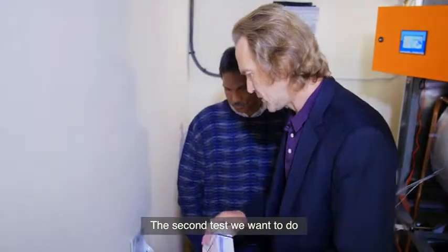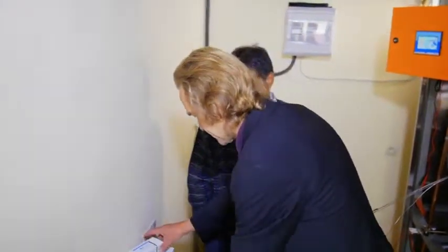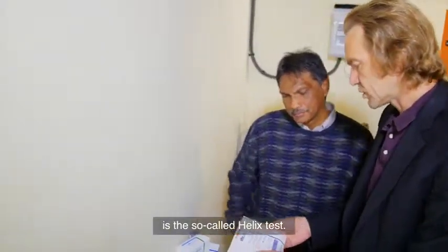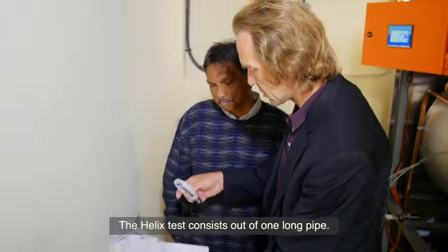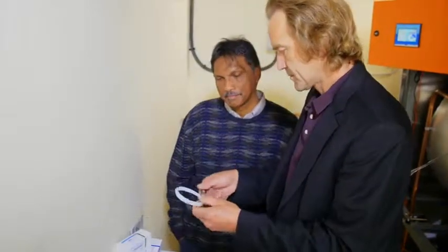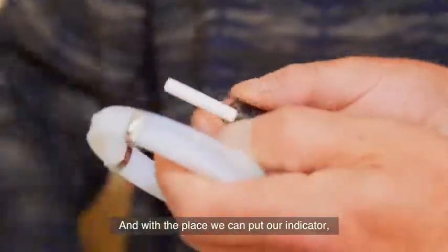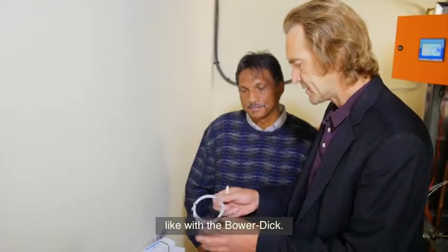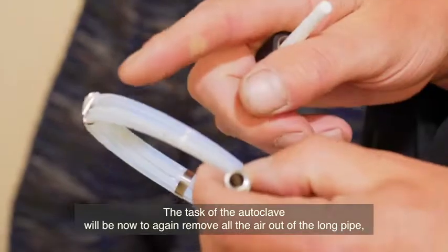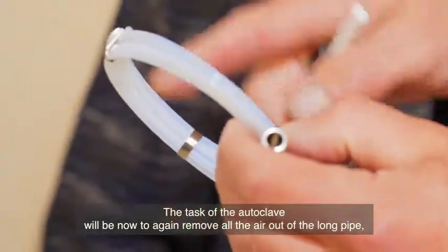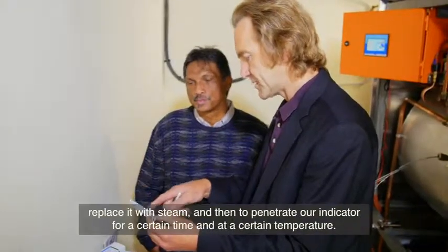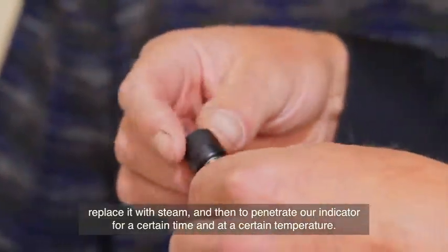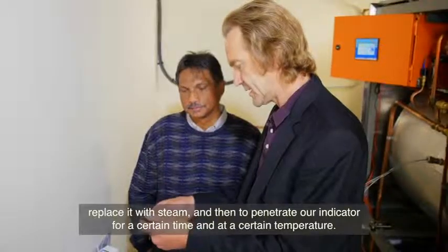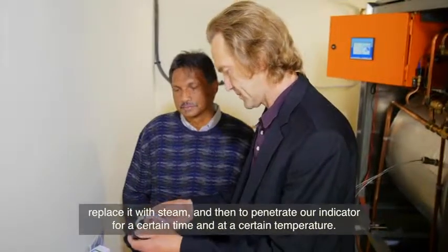The second test we want to do is the so-called helix test. The helix test consists of one long pipe and a place where we can put our indicator, like with the Bowie-Dick. The task of the autoclave will now be to remove all the air out of the long pipe, replace it with steam, and then to penetrate our indicator for a certain time and at a certain temperature.